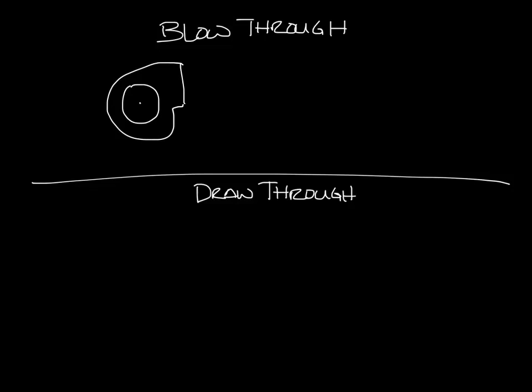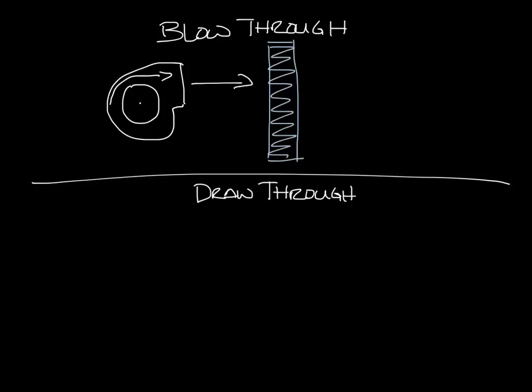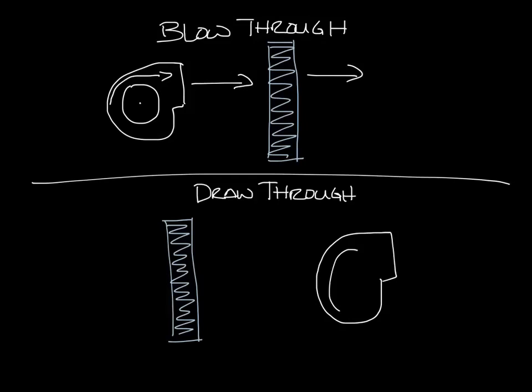So let's draw a blower here. And we'll put, in this case, a cooling coil over here. Now the air is coming out of the blower and is blowing through the water coil. So that is a blow-through configuration. Down here, let's look at the draw-through. So in this case, you've got your water coil first and your blower over here. And it's going to pull air and draw it through the water coil.